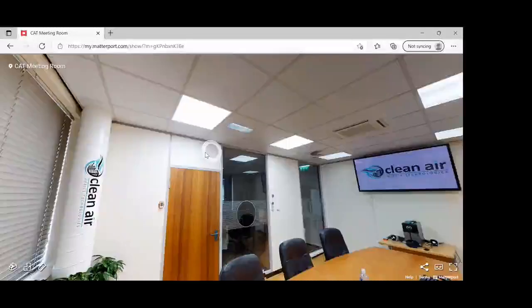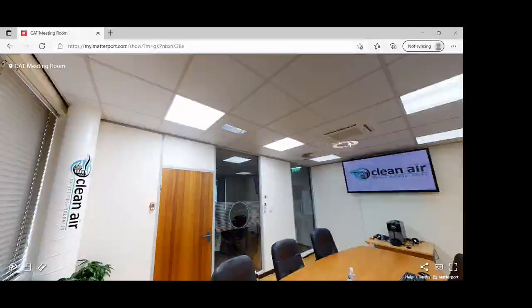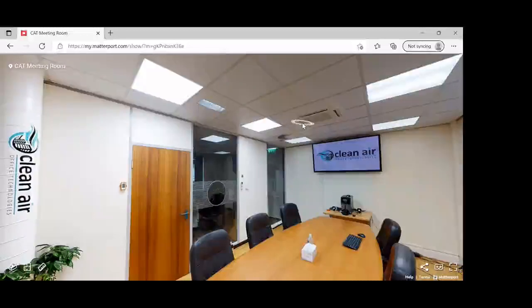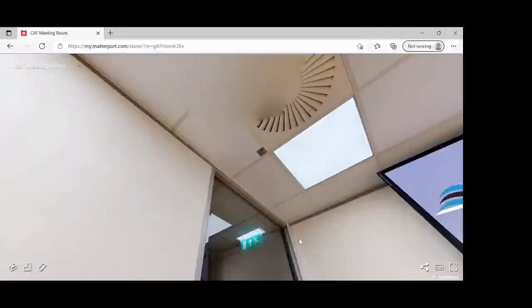It's basically designed to work in tandem. So you can see up here, we've got a cassette unit. One of the tests that we carried out was to make sure that the airstream coming off the fan filter unit, the air conditioning unit up here, wouldn't overpower what you can see up here, which is a swirl diffuser, which we've taken directly from the cleanroom industry.